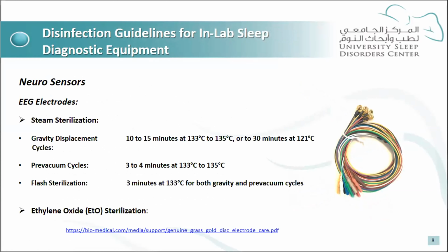So those are the respiratory sensors. Now we will be talking about the neurosensors. With neurosensors, we mainly talk about the EEG electrodes. For EEG electrodes, we have different ways of disinfecting. We have the disinfectant, like Cidex, which you can use. And we have stronger sterilization: steam sterilization, as well as ethylene oxide sterilization. Mainly, steam sterilization is the most recommended one. And we have mainly two options: the gravity displacement cycle and the pre-vacuum cycle.